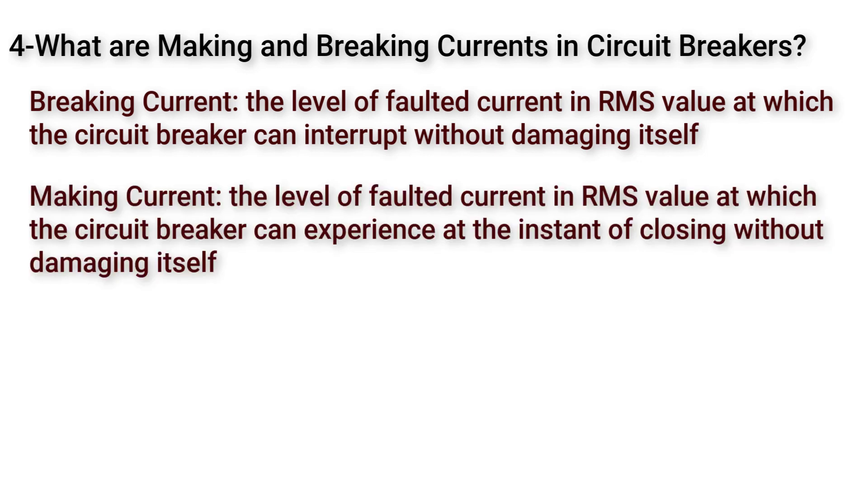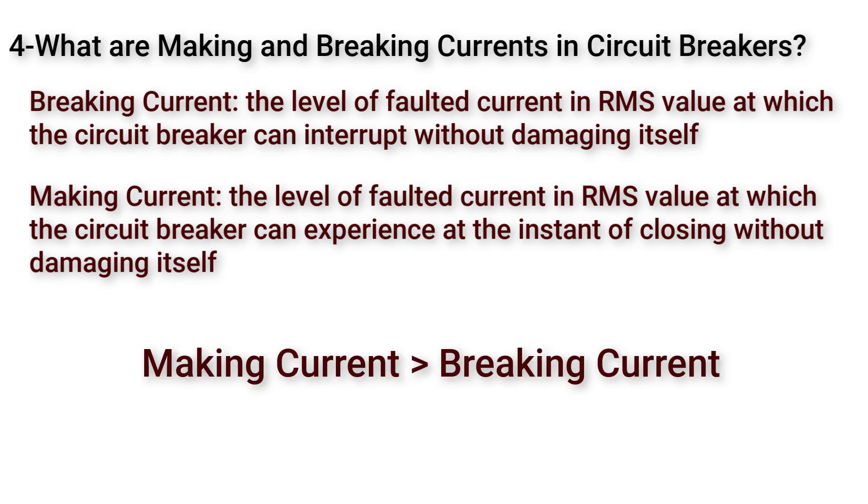What are making and breaking currents in circuit breakers? Breaking current is the level of faulted current in RMS value at which the circuit breaker can interrupt without damaging itself. Making current is the level of faulted current in RMS value at which the circuit breaker can experience at the instant of closing without any damage to itself. So the making current of circuit breaker is usually greater than the breaking current of circuit breaker.